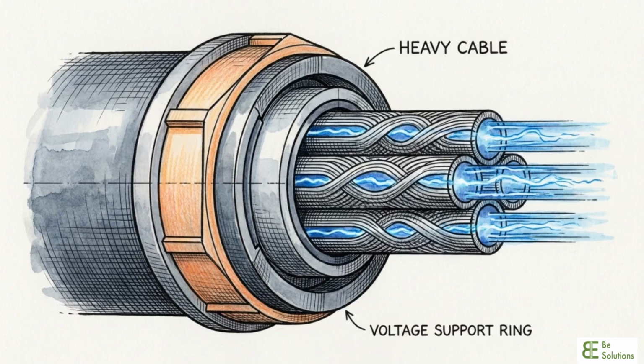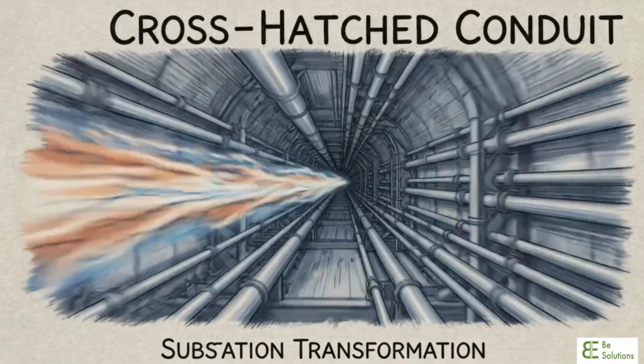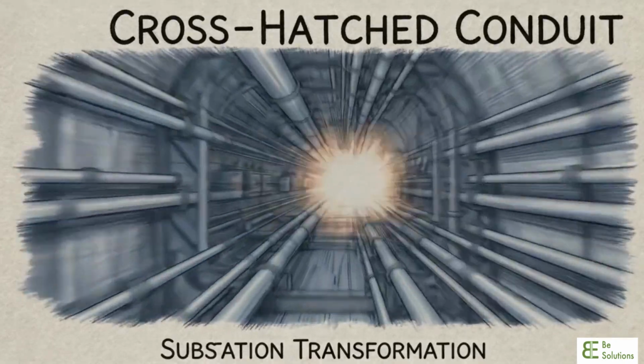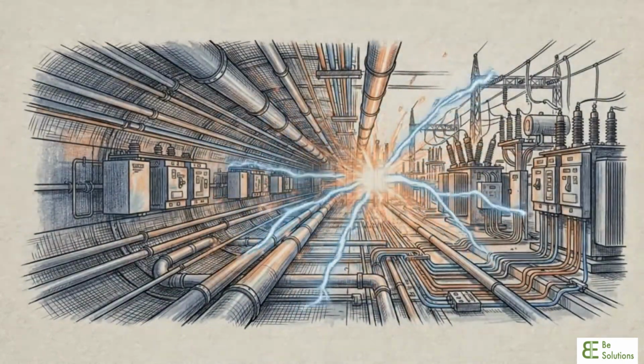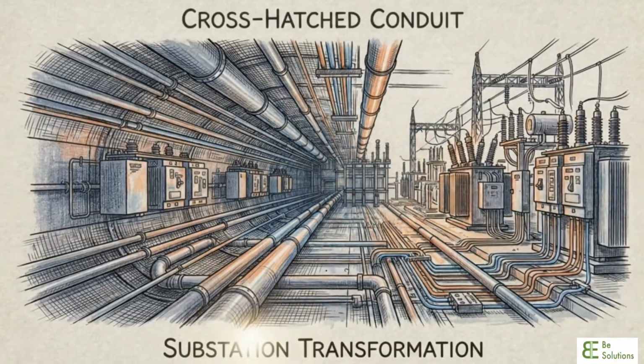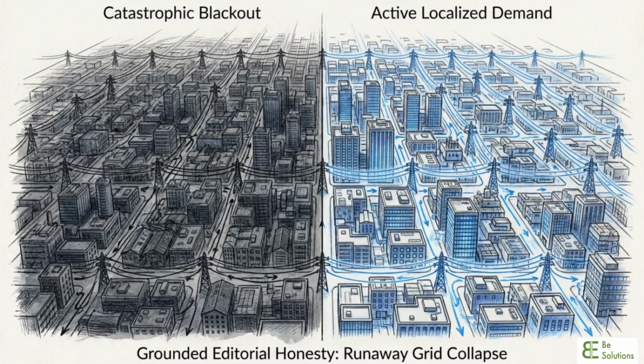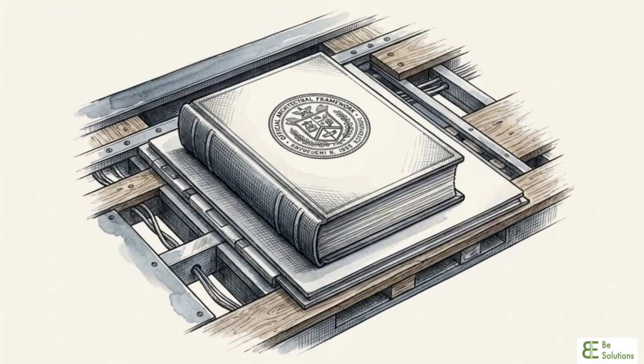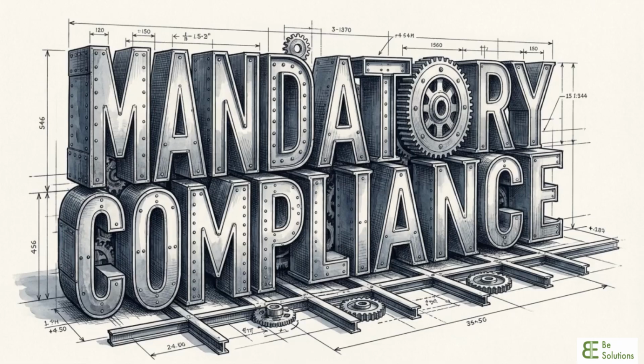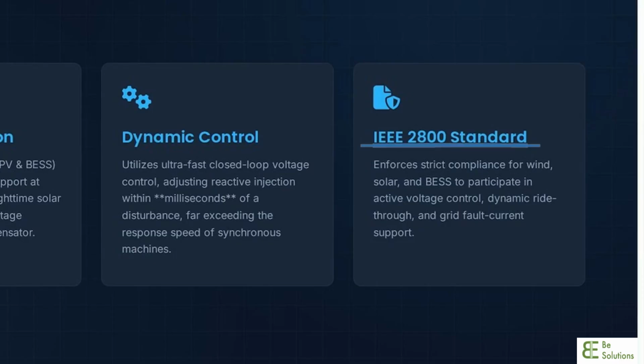During a transient grid fault, system voltages plunge. Inverters must immediately inject dynamic reactive current to recover the voltage curve. If the localized demand for reactive power exceeds the supply, it triggers a runaway effect, resulting in a sudden, catastrophic regional blackout. Because these outputs are entirely synthetic, utility regulators have established the IEEE 2800 standard. This chart shows the specific obligations enforced by IEEE 2800.